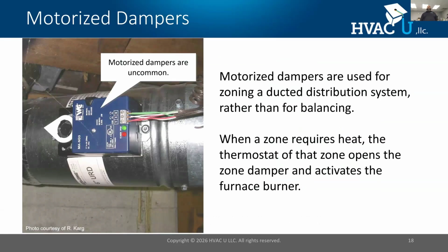in order. Now, one thing that we've done to help customers is to, in addition to balancing, go with zoning. Zoning is a way to satisfy some uncomfortable areas. This is my favorite solution when I'm dealing with a home that's maybe 2 stories. I have a large home, and let's say I got one system servicing that home and it's located in the basement. What happens on the first floor, even if the ducts are sized correctly, the thermostat is on the first floor and it satisfies way before the airflow can get up and satisfy the second floor.